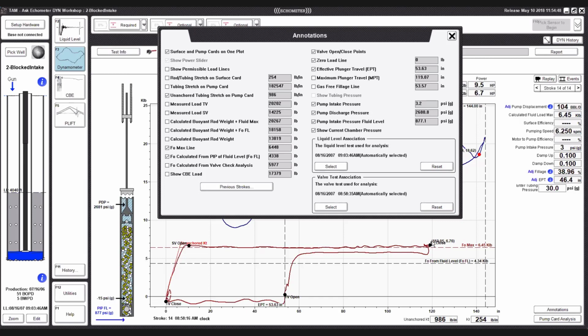Now we're at the top of the stroke, and we have a certain pump discharge pressure that we have to overcome. The pump intake pressure, or the pressure in the chamber, is very low. It shows minus 15. So we have to compress everything that's in the pump. We see it compressing on the downstroke, and we see the number increasing very slowly because there's not much in there to compress.